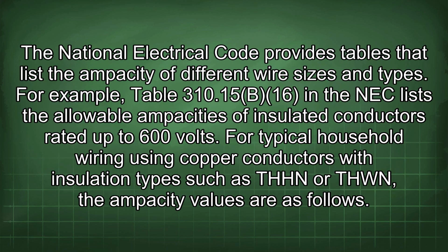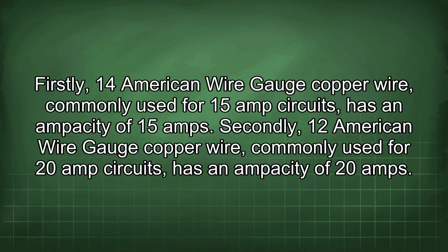The National Electrical Code provides tables that list the ampacity of different wire sizes and types. For example, Table 310.15(B)(16) in the NEC lists the allowable ampacities of insulated conductors rated up to 600 volts. For typical household wiring using copper conductors with insulation types such as THHN or THWN, the ampacity values are as follows. Firstly, 14 American wire gauge copper wire, commonly used for 15 amp circuits, has an ampacity of 15 amps. Secondly, 12 American wire gauge copper wire, commonly used for 20 amp circuits, has an ampacity of 20 amps.